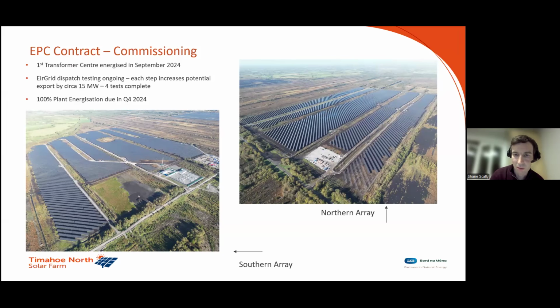As part of that process, we're conducting an ongoing series of dispatch testing with EirGrid and Voltalia. At each step in the dispatch test process, we increase the export potential of the farm by about 15 megawatts. We've 4 tests complete, so we're up around the 60 megawatt mark now. With the nice sunny weather in Ireland at the minute, we're not achieving anywhere near that, but when the sun comes out, it's amazing how quick the farm will run up in the energy stakes. As Connor alluded to earlier, it's optimized for summer production, so during the winter time we have that challenge of trying to get production while doing the tests - we do need energy to carry out the dispatch test. Hopefully we'll get a bit of sunshine for the next couple of weeks as we look to get the plant fully online, which should happen, as Martin said, later this month, hopefully, all going well.